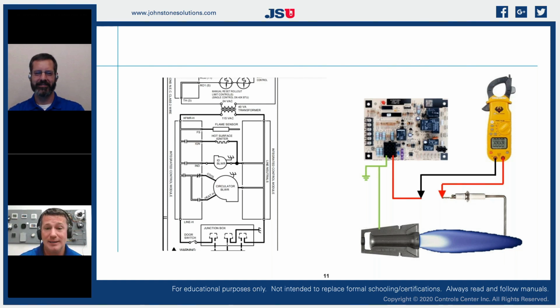If we look at the wiring diagram, on the left is a wiring diagram from a Goodman furnace. Simply looking at the wiring diagram, we can prove the philosophy. My flame sensor, which is just a flame rod, is on the 115 volt side of my circuit. It's on the high side of my transformer. It is in the exact same power supply as my hot surface igniter, my induced draft blower, and my circulating blower. So it is 100% on the high side of my circuit.